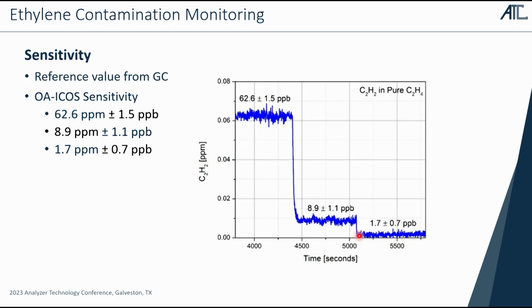As it continues to fall, we're down to less than 2 part per million, which is below the LOD. And I should back up here, and we define an LOD as the lowest level which you can guarantee a calibration will work, not the lowest level the analyzer can see something. And there's a huge difference in those two concepts. But we're down below the manufacturer's specification for the LOD, and we have a sensitivity of 0.7 part per billion.